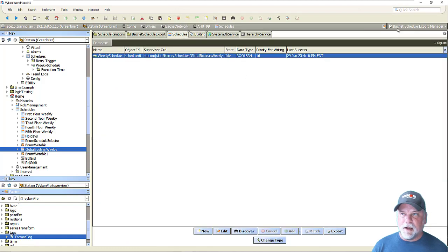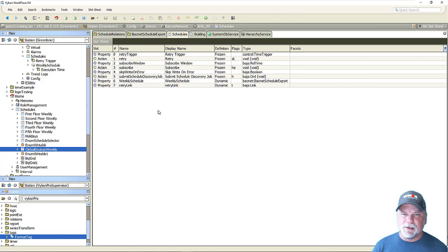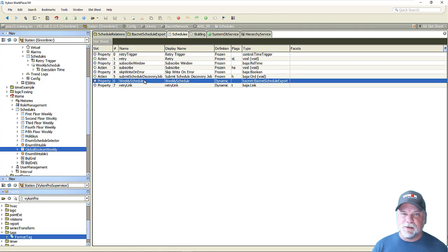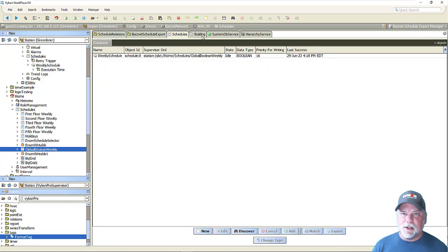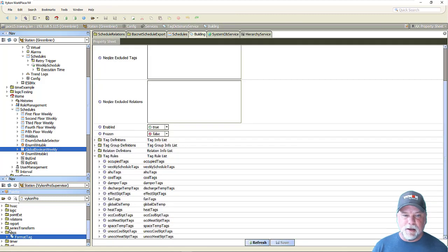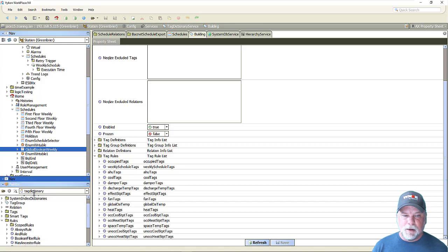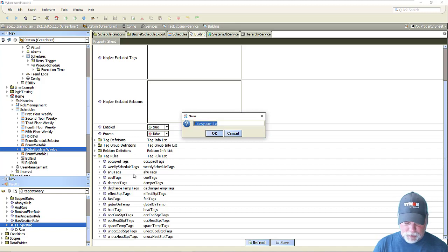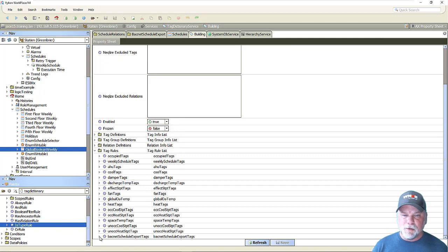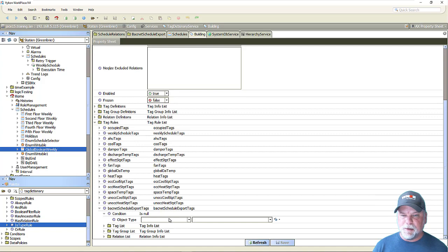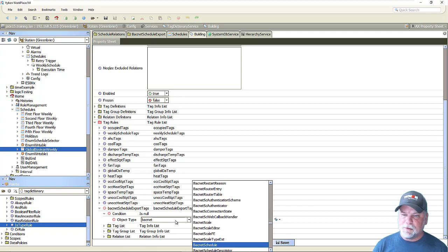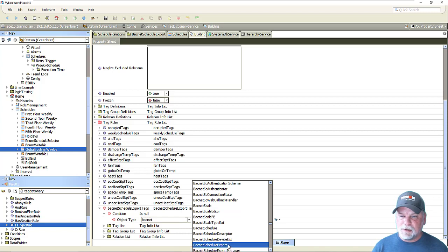Taking a look at the AX slot sheet of the schedule device extension, I can see that this weekly schedule export object comes from the BACnet module and it's a BACnet schedule export. So the tag rule we need to create is to assign tags to that BACnet schedule export. Going into the tag dictionary and then the rules folder, I'll get an 'is type' rule and drag it out, and we can call this 'BACnet schedule export tags'. For this tag rule, under the condition, it's going to be a type condition with a type spec selector — I can pick the BACnet module and then look for BACnet schedule export types.